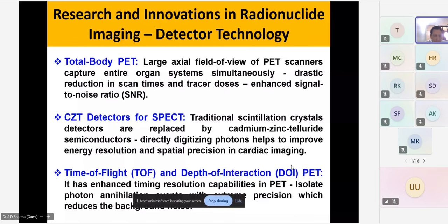The use of cadmium zinc telluride detectors for SPECT. Earlier, as we are all aware, traditionally we used scintillation crystals or detectors in SPECT systems. These detectors are nowadays replaced by cadmium zinc telluride detectors, which are basically semiconductors.